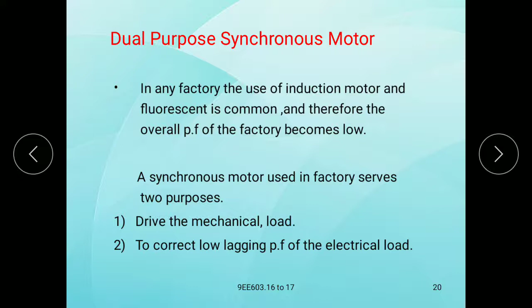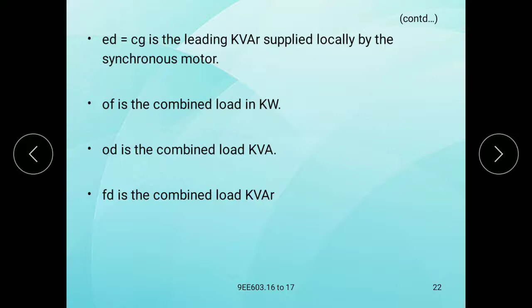Here OB is equal to load KVA, OA is load KW, AB is the load KVAR, BD is the synchronous motor KVAR, and OG is the motor load in kilowatts. Now ED is equal to CG, the leading KVAR supplied locally by the synchronous motor. OF is the combined load in kilowatts, OD is the combined load KVA, and FD is the combined load KVAR. As from figure 4, the power factor of the system is improved from cos phi 1 to cos phi 2. So now problem 2.